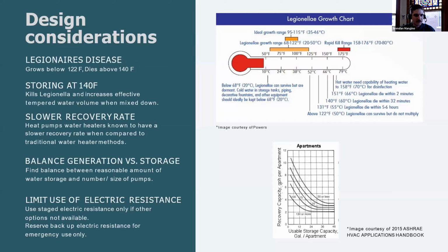Another good thing about storing at 140 is it gives us a little bit more effective tempered water volume, because we'll be mixing that down to our target delivery temperature. Another thing to consider with heat pump water heater systems is that they have a slower recovery rate when compared to a more traditional natural gas or fossil fuel boiler system. So when you're designing these systems, you have to play the game of storage versus recovery rate, and you can balance that. At the bottom you can see a sizing chart from ASHRAE's HVAC Applications Handbook. I always try to balance how much storage we have in the project versus how much heat pump generation we have.